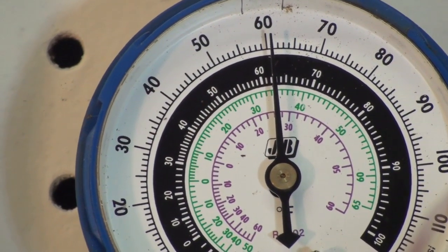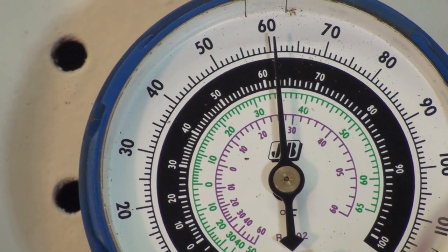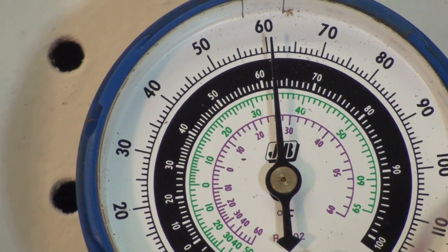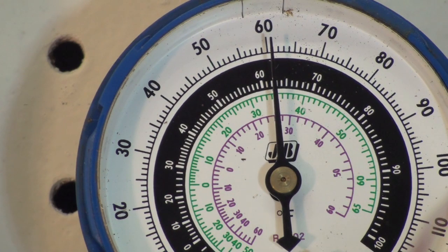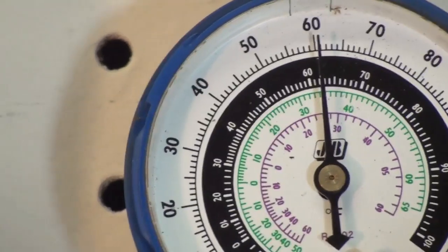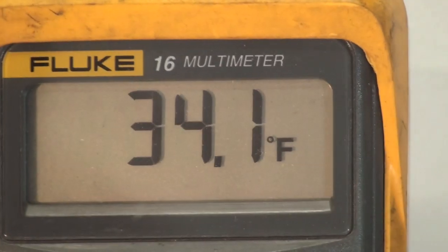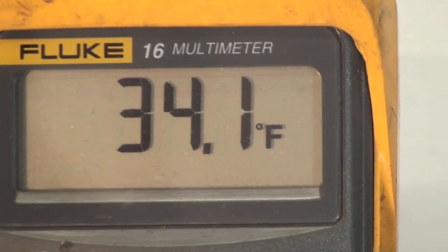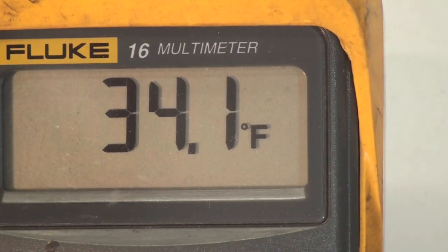Okay, looks like we're about 61 and right at 35 degrees. 61 equals right about 35 degrees. Okay, let's go over and look at what the temperature probe says. It says 34.1. It's an accurate representation of what the temperature is.